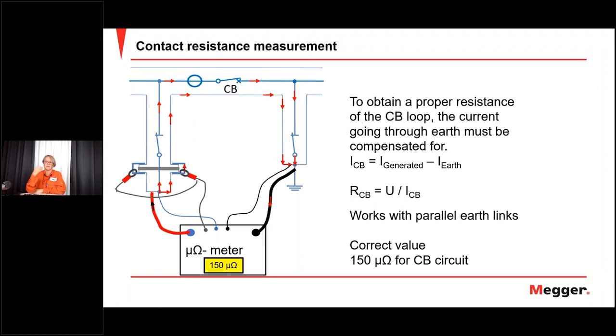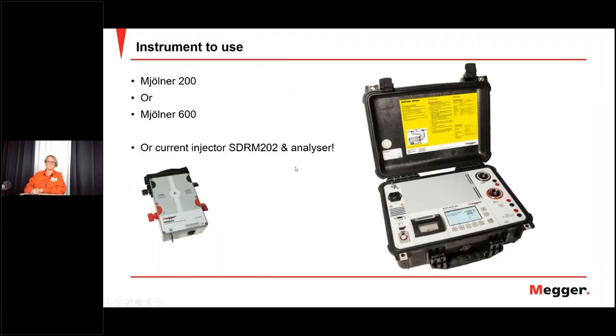But again, you don't only measure the circuit breaker, it's the circuit breaker circuit. It's not only the circuit breaker here. It's all these bars. And as soon as you have another component like this, and also, of course, the bars themselves and the intersections here, you will get resistances. So this is the total resistance from here to here. To do this, you can work either with a Mjölner, and of course, if you need as much as 300 amps, you need the big Mjölner 600. And otherwise, you can work with Mjölner 200 or the SDRM, which are both 200 amps.